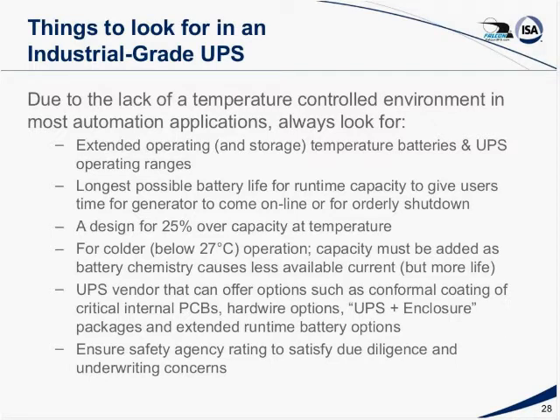You want the longest possible battery life for runtime capacity to give users time for the alternative or generator to come on or for orderly shutdowns. You should always design the 25% overcapacity in mind, because of the temperature extremes you'll operate at. That means if you're going to be below 27 C, you have to add capacity because the battery chemistry will cause less available current. However, they will last longer. Of course, we've already discussed, and we'll continue to discuss, the fact that if you are above this, then you're going to have less life. But in any case, you need to make sure that you have 25% more capacity than you think you're going to require.